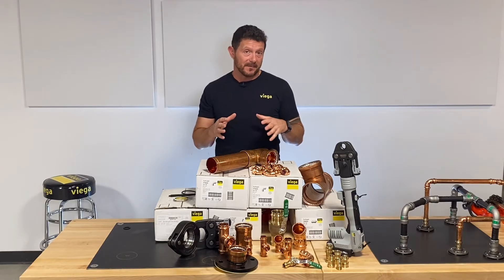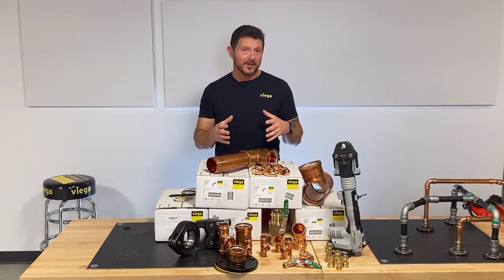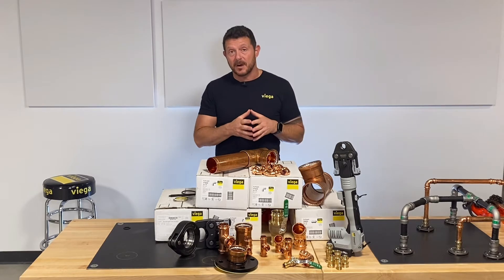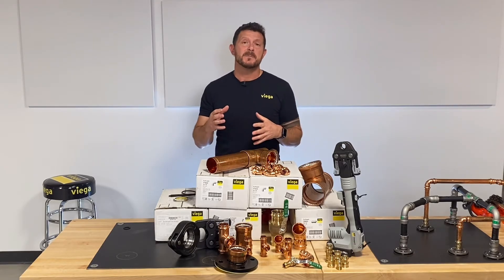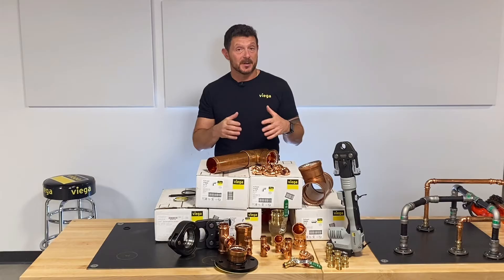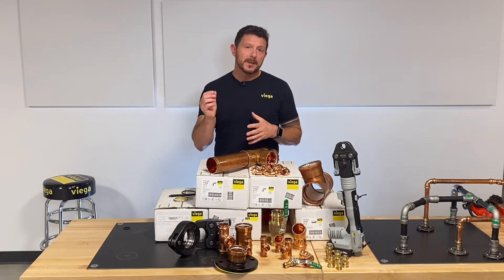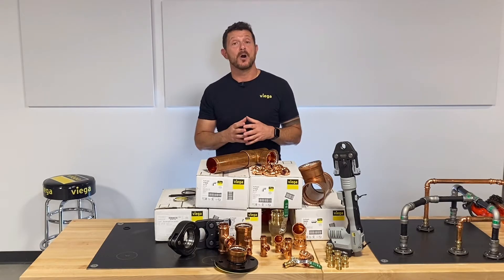Viega ProPress fittings are manufactured in the United States of America and Germany from heavier than type K copper. They're either hydroformed — T's are hydroformed — or elbows, which are mandrel bent. This provides a really smooth internal profile to the fitting, much smoother and much less turbulent than a comparative copper solder fitting, and you get a really uniform wall thickness throughout the fitting, so the fittings are really strong and durable.